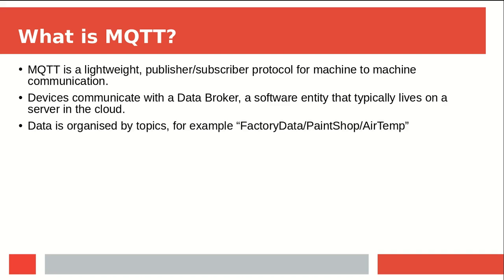The data the broker handles is organised by topics. These are formatted into levels, and you can subscribe to a specific topic such as factory/data/paint-shop/air-temperature, which would give you the temperature of the air in the paint shop. Or you could subscribe to a more general level — so you might ask for all the sensor data from the paint shop, which would include temperature, humidity, the amount of time the paint gun has been in use, and so on. Equally, you might have data from other parts of the factory, such as the machine shop or the warehouse.